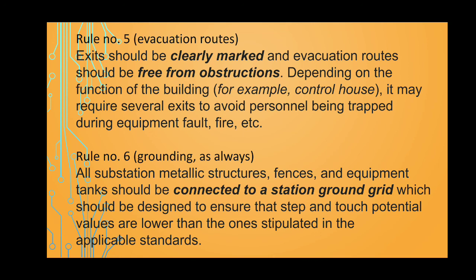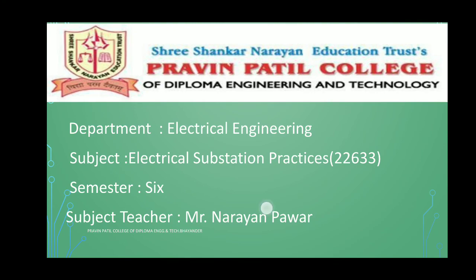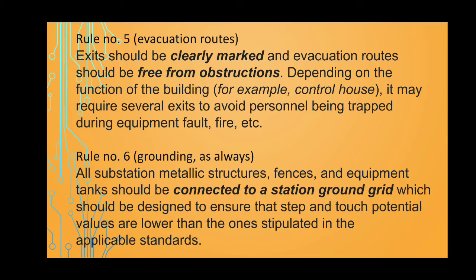Next, rule number 6, grounding. All substation metallic structures, fences and equipment tanks should be connected to the substation ground grid, which should be designed to ensure that step and touch potential values are lower than those stipulated in the applicable standard. So these are also essential rules of electrical safety precautions which provide protection to electrical systems. So these are the different rules and safety precautions carried out in an electrical substation.